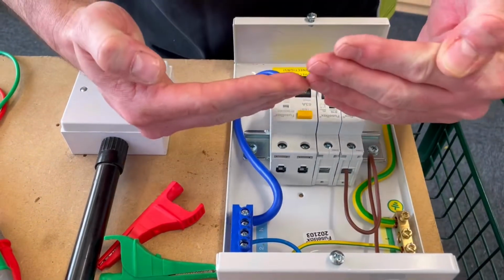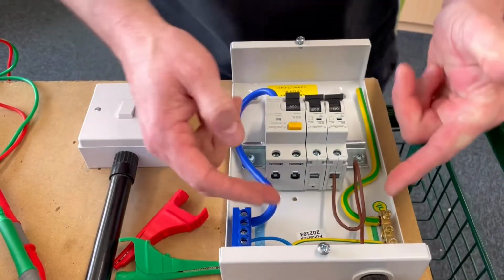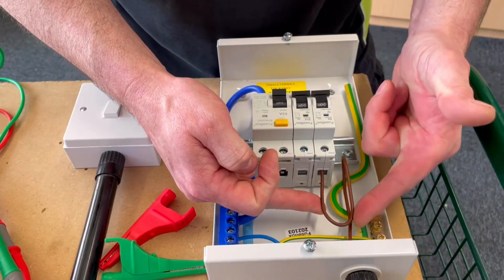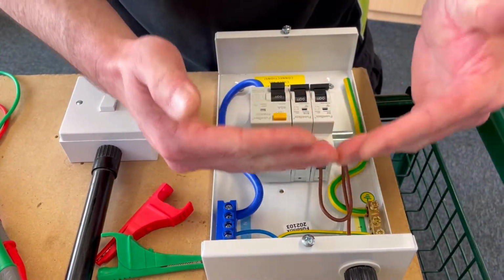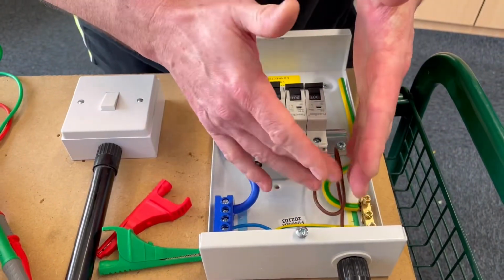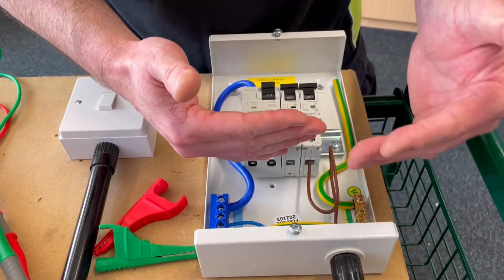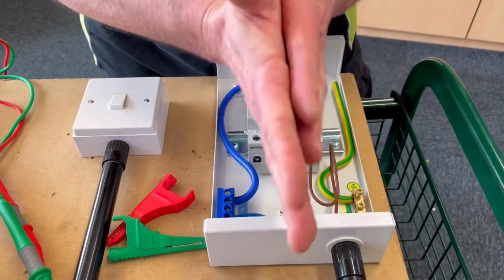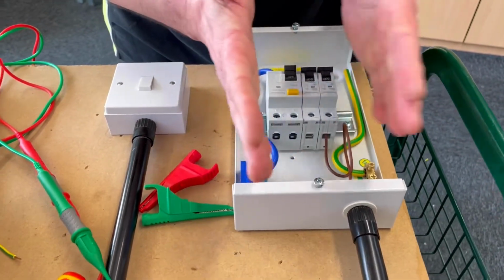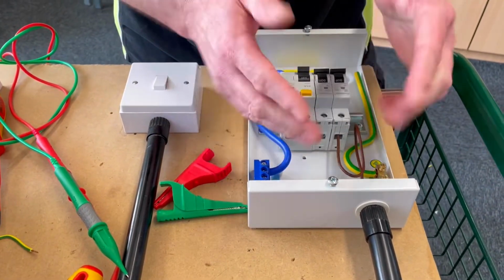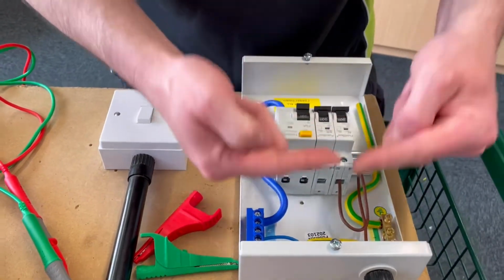And we would expect this reading to be massively high. So what we're trying to prove is that the insulation around our conductors has not degraded between them. So we don't expect these to have broken down over time, or perhaps friction caused them, when pulling in, to rub against each other, and the insulation between them is starting to break down. These are brand new cables.